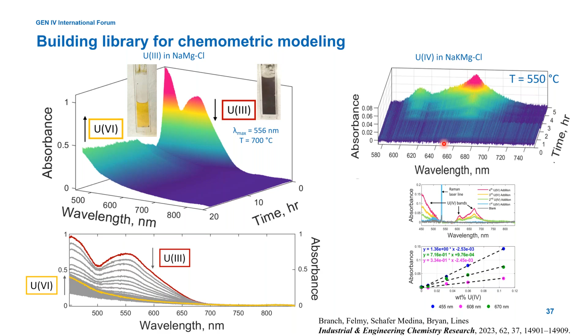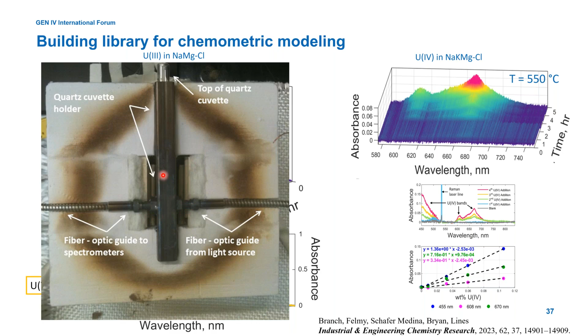This shows some of the variable absorbance measurements that we use for our training set. And this image here shows our small-scale cuvette that we use to go ahead and measure the system that we use to measure the absorbance spectra and the Raman spectra of these salts. This shows a cutaway of our furnace that we have our cuvette within the cuvette holder shown here. We have the fiber optics, the light guide coming in and the light guide going out to the detector here. And so we have a quartz cuvette in this case, that's here. And so we can use UV vis for transmission. We also have ports that we can put Raman probes for light scattering and Raman measurements in this as well.